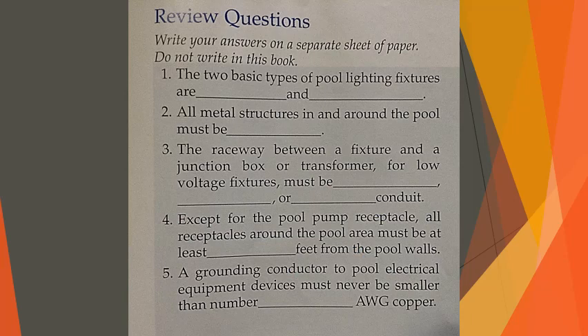Moving on to the review questions for this chapter. Number 1, the two basic types of pool lighting fixtures are wet niche and dry niche. Number 2, all metal structures in and around the pool must be bonded. Number 3, the raceway between a fixture and a junction box or transformer for low voltage fixtures must be rigid, IMC or intermediate metal conduit, or other approved corrosion resistant metal conduit. Number 4, except for the pool pump receptacle, all receptacles around the pool area must be at least 10 foot from the pool walls, and they also must be GFCI type. Number 5, a grounding conductor to pool electrical equipment devices must never be smaller than a number 12 AWG copper.